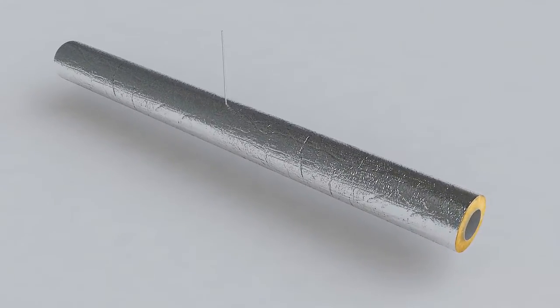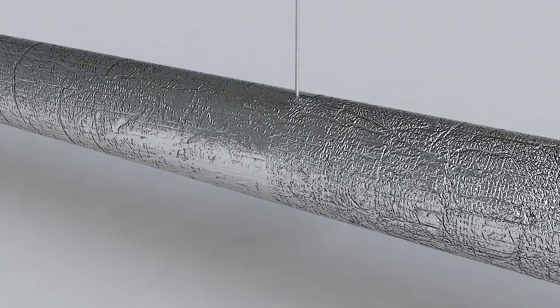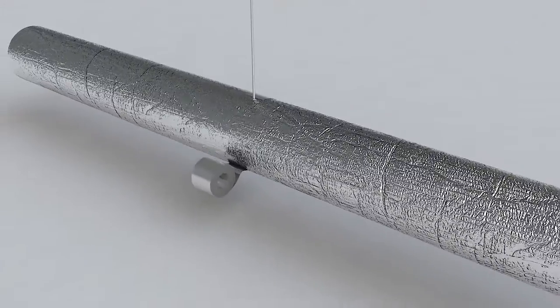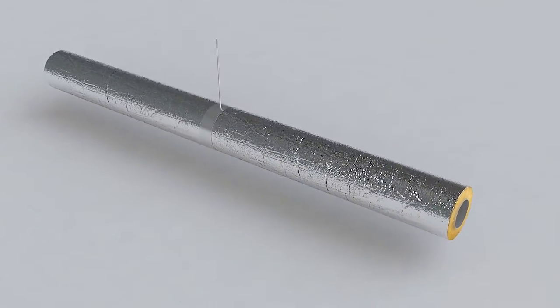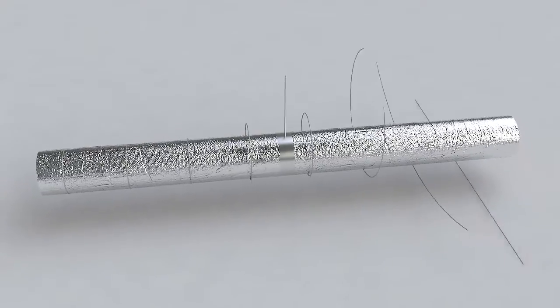With ducts that carry chilled or cold air, all transverse seams should be taped tight using AL Installation Tape. Finally, the insulation is secured with binding wire at 300 millimeter intervals. Then the insulated duct is ready to be installed.